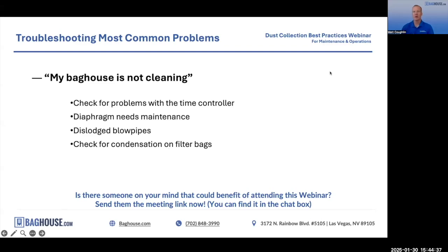So what I'll do is I'll go out and I'll stand there by the baghouse and I will listen. Now, if you have your timer set up on just a continuous mode, you know that at every 20 seconds it should fire. If it's not firing, well, then you can pretty safely say that either your timer board isn't working. Usually you can go look at it and see it'll have little visual indicators when each output fires. So check that. An electrical connection between your timer and your solenoid.